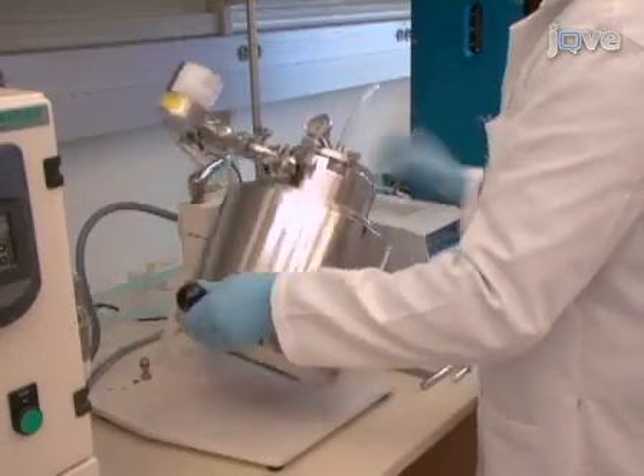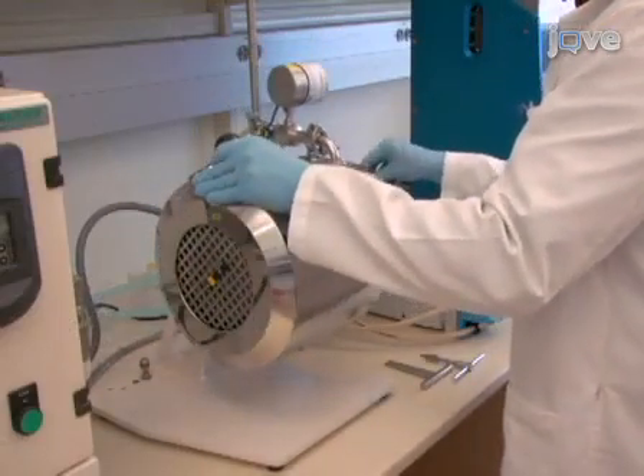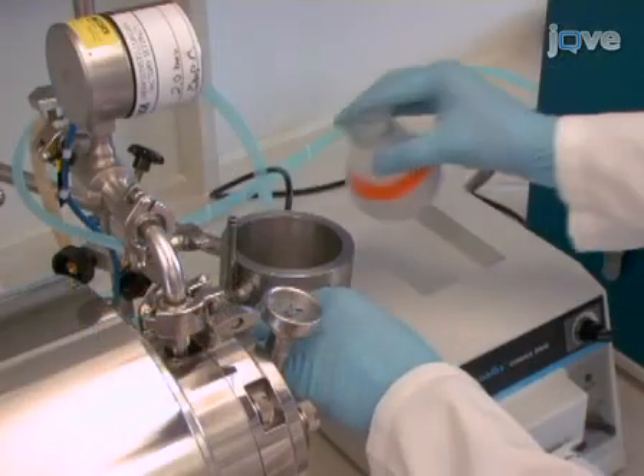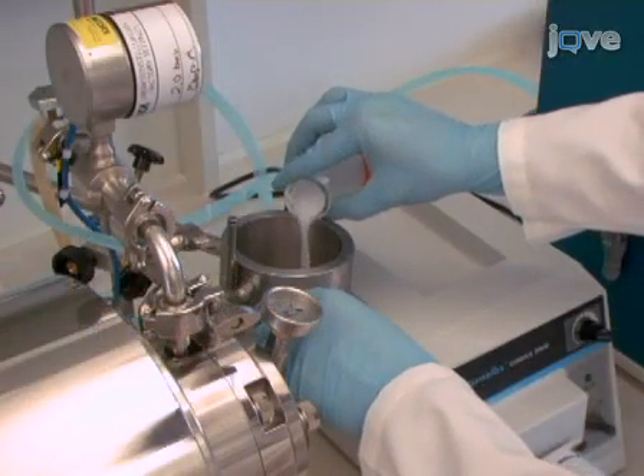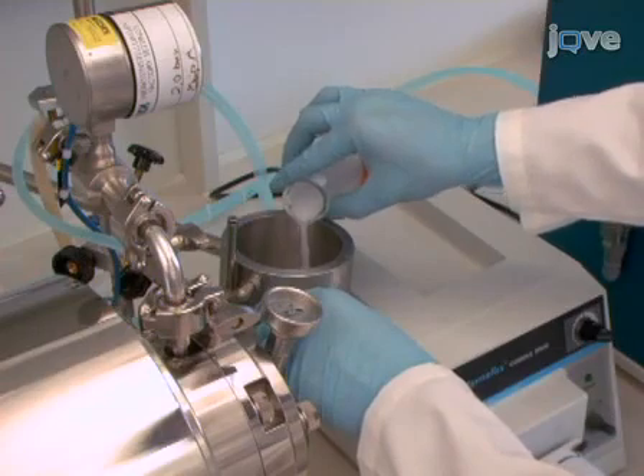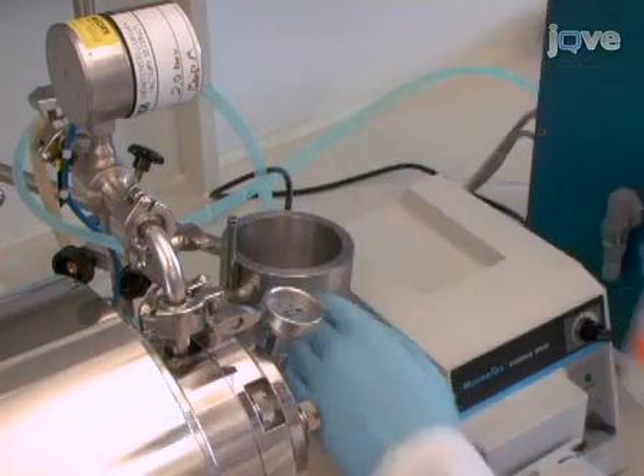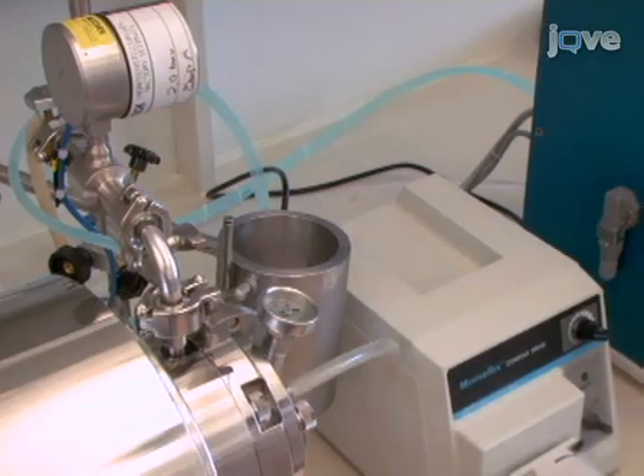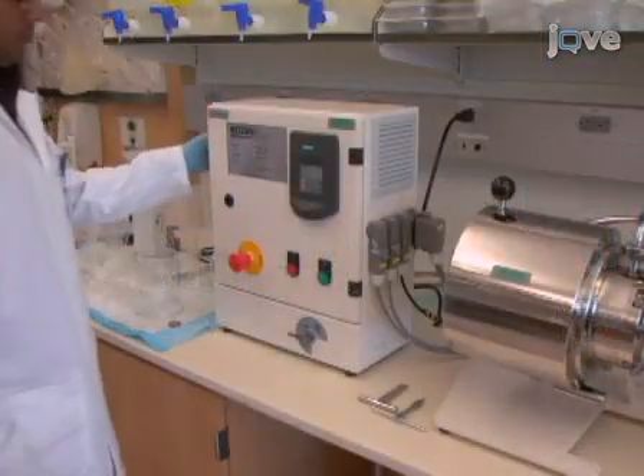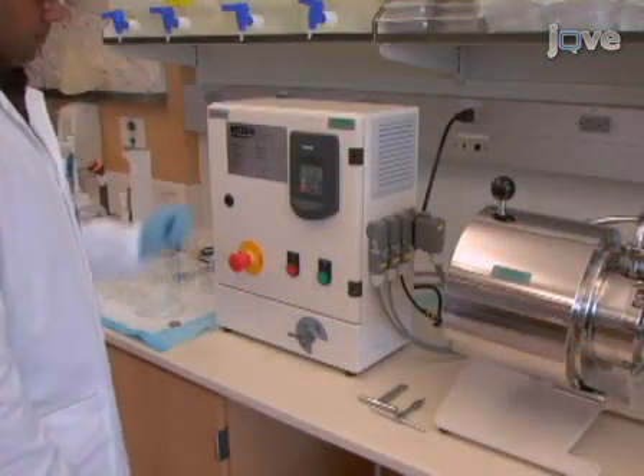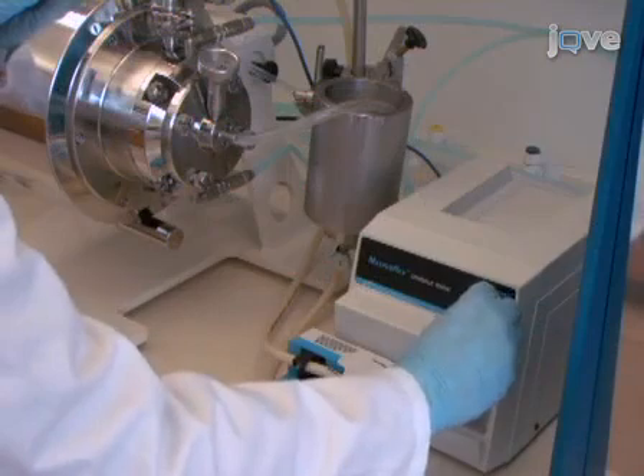After lowering the grinding chamber, add the drug suspension with various amounts of surfactants to the product inlet. The minimum volume of the suspension should be 100 milliliters. This will prevent the milling chamber from overheating and also avoid bead contamination due to less wear on parts. Next, start the pump using the control unit, varying the flow rate as required for your formulation.